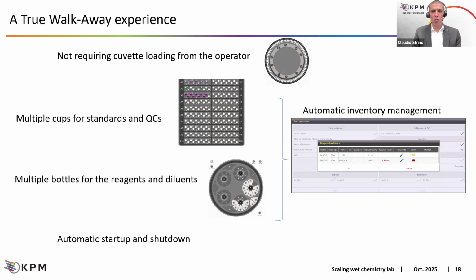We spoke many times in the previous slides about the true walk-away experience that we can have by using the SmartCam. And what are the four main factors that allow us to speak about a true walk-away experience? Because different from other instruments available in the market, thanks to reusable cuvettes, the instrument is not requiring any cuvette loading from the operator, because the cuvettes will be washed and reused. We have the possibility to load multiple cups for standards and QCs. That will guarantee us to have enough liquid also for QCs to cover very, very long routines. We have the possibility to load multiple bottles for reagents and diluents in the reagent compartment. And the instrument will directly manage to use the next bottle when the one in use is empty.